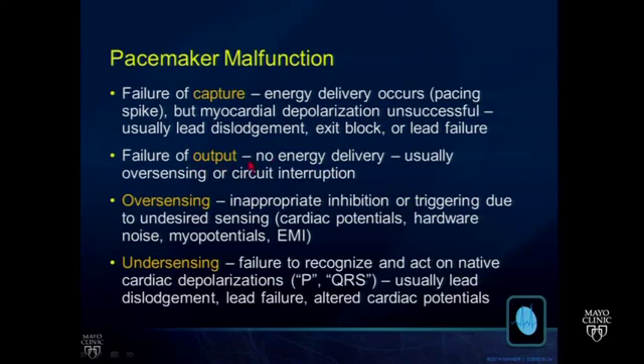With failure of output, the circuit is not closed. We do not deposit energy on the myocardium. So there will be no pacemaker spike with failure of output. And this is usually due to the third category of malfunction, oversensing, or an actual interruption in the circuit of the device.